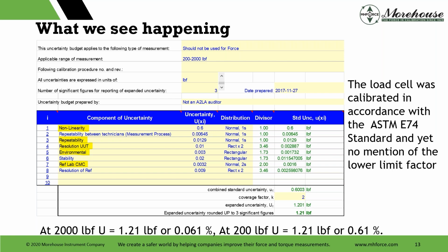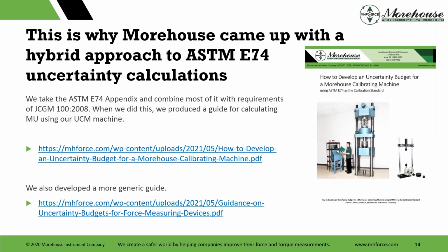The other thing is this, what I was getting at, and kind of bumbled a little bit, but it was at the percentage. You say, okay, 1.21 pounds is on the scope. Okay, fine. And then they say, okay, well, that's 0.6. Well, I'll round this up to 0.65 and I'll put that on my scope. However, that number right there is constant, and at 10%, 0.061 becomes 0.61. So we see a lot of that stuff going on too, is that you're not taking the full range and just converting into a percentage, but that percentage is only of that actual value, and this one at 2,000 pounds. Just things to think about.